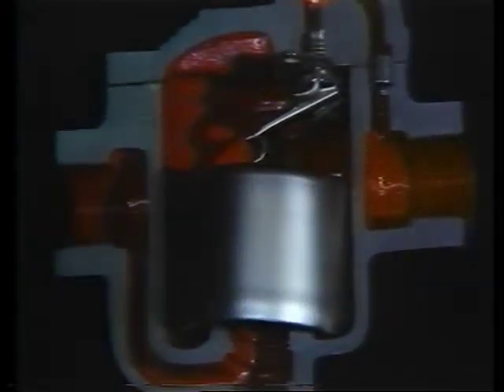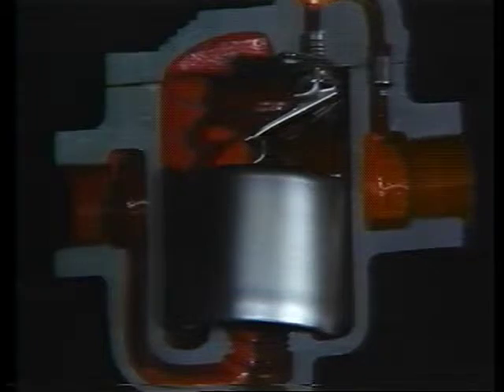For many years, the textile industry has used the Armstrong inverted bucket trap in conjunction with a stationary siphon pipe to drain rotary cylinders. The inverted bucket has an intermittent discharge that purges air and condensate from the cylinder, while air is continuously vented through the bucket vent. The simple yet extremely rugged construction of this trap allows it to provide a long, trouble-free service life.